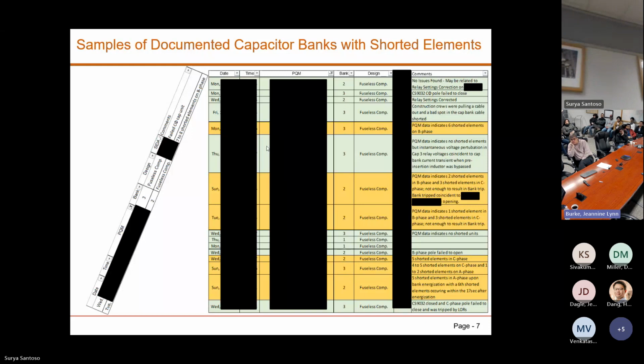This is which power quality monitor, this is which bank that has the shorted elements, and this is the capacitor bank design. Eventually it tells you that, based on the field analysis, there are 5 shorted elements in the A phase, or there are 4 to 5 shorted elements on C phase and 1 to 2 shorted elements on A phase, like that.